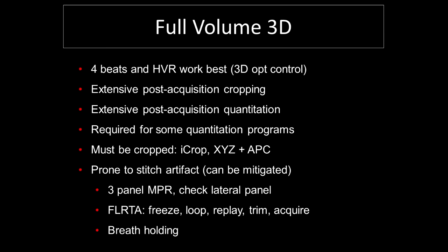For full volume 3D in children, we almost always use a four-beat acquisition — it's the best balance between resolution and frame rates. Occasionally we use the high volume rate on the 3D opt setting. If you have an older version of QLab, you may notice that HVR images cannot be used to measure ventricular volumes. Later versions you can, earlier versions you cannot. Make sure that if you're using full volume 3D to do an LV or RV volume with the HVR setting, you have software version 10, 11, or greater.